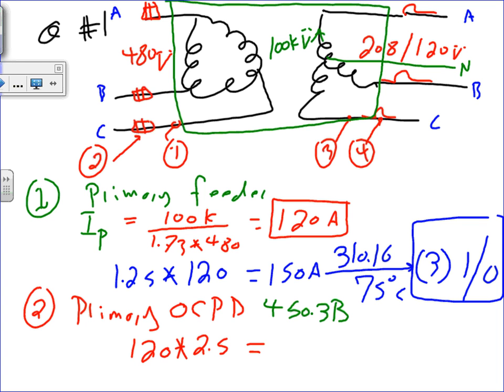No, I understand why we're using table B. I'm wondering why we're not using the 150 amp instead of the 120. The 150 is because it's multiplied by 1.25. That's just the size of the cable. You always start with the actual amp, the transformer amp. The 150 is the cable amp.